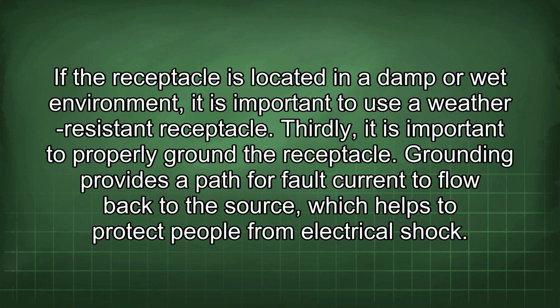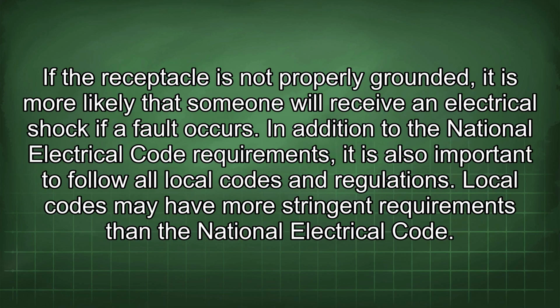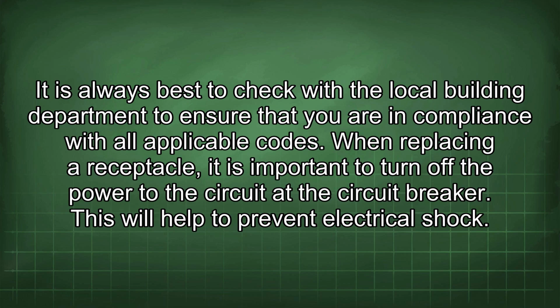Thirdly, it is important to properly ground the receptacle. Grounding provides a path for fault current to flow back to the source, which helps to protect people from electrical shock. If the receptacle is not properly grounded, it is more likely that someone will receive an electrical shock if a fault occurs. In addition to the National Electrical Code requirements, it is also important to follow all local codes and regulations. Local codes may have more stringent requirements than the National Electrical Code. It is always best to check with the local building department to ensure that you are in compliance with all applicable codes. When replacing a receptacle, it is important to turn off the power to the circuit at the circuit breaker. This will help to prevent electrical shock.